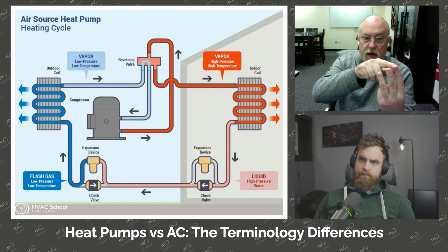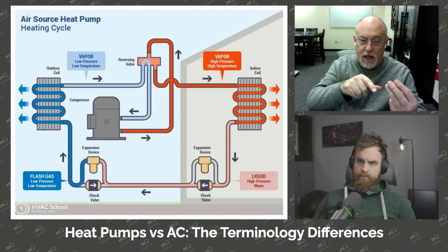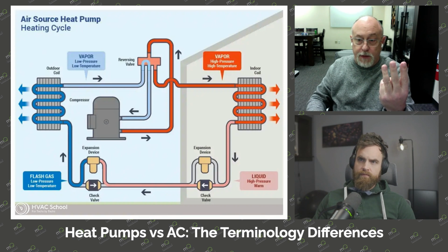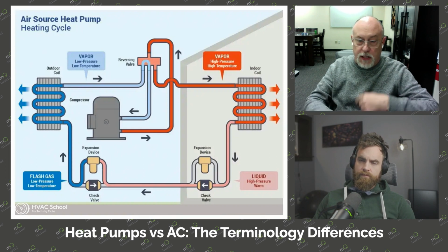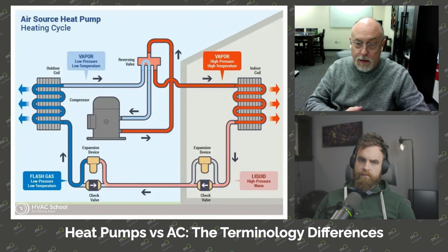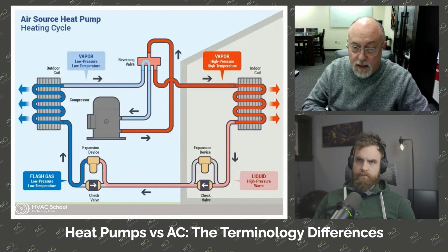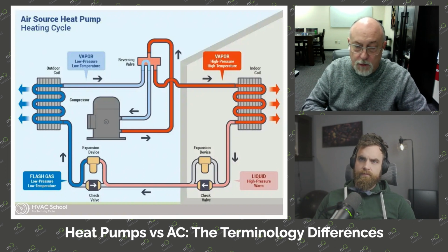Whether the two other ports can swap, so that they could direct hot gas to either one, depends on how the manufacturer set it up. If you ever replace a reversing valve and put it in backwards, you'll change the whole configuration of the heat pump, because it'll flow the gas in the wrong direction. So it's really important to understand how your reversing valve works.